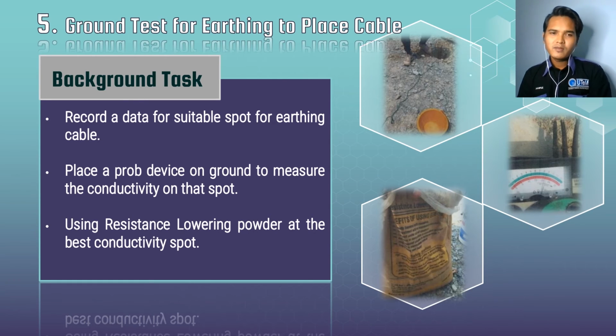Place the probe device on the ground to measure the conductivity at that spot. To place the probe rod, you need to be careful because the rod is sensitive, and the ground needs to be wet first.